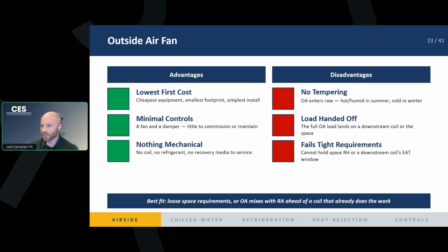You don't get any tempering. There's no cooling or heating. Raw outside air enters your space. Maybe that's okay. Maybe that's not. Most of the time, that is a disadvantage, though. But if you're not dumping it directly into the space, you are just handing that outside air load downstream to that secondary coil, right? You're mixing it with the return air, but that load still needs to be captured by that downstream coil, which results in a larger coil downstream. Whereas the other types of systems we're looking at, you don't need as big of a coil in that downstream system. And you're going to fail to hold a tight space temperature and humidity.